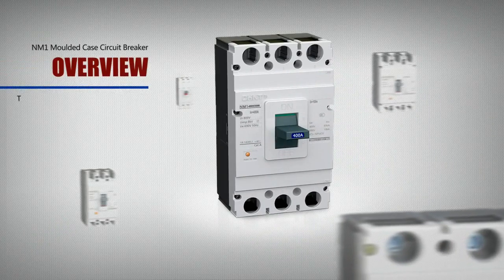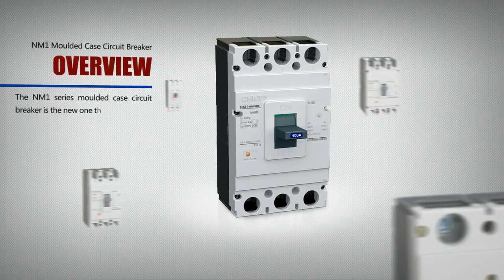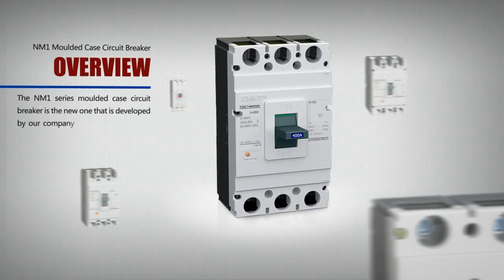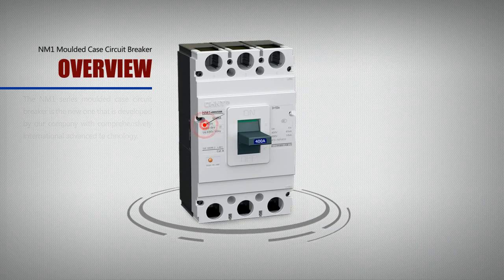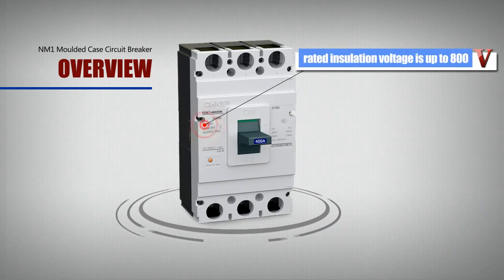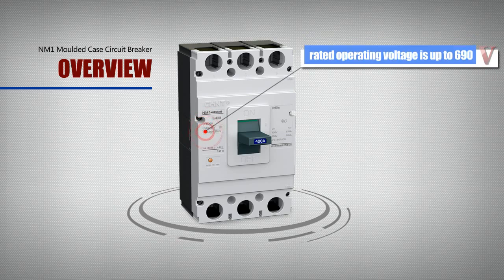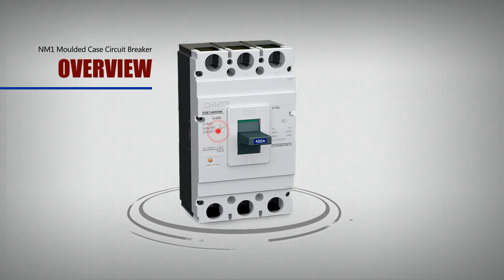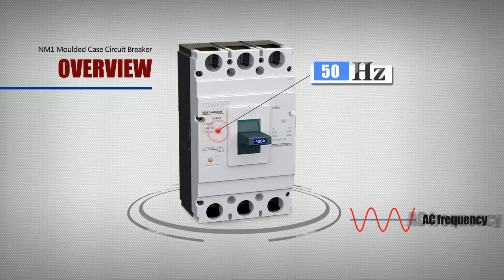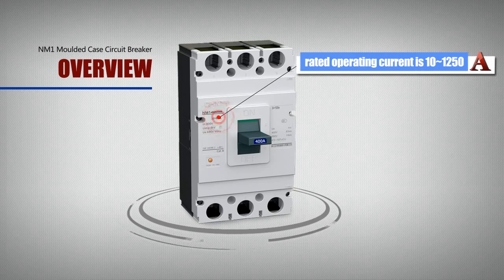The NM1 series molded case circuit breaker is the new one developed by our company with comprehensively international advanced technology. Its rated insulation voltage is up to 800V, with the 63 model at 500V. It is suitable for power distribution network circuits in which the rated operating voltage is up to 690V, AC 50Hz, and the rated operating current is from 10A to 1250A.